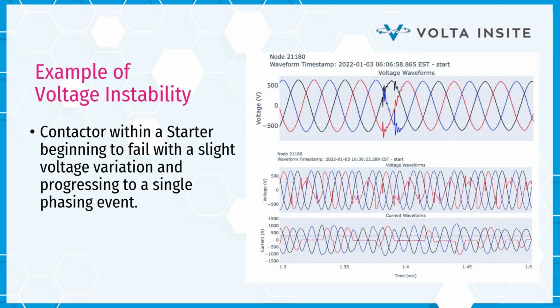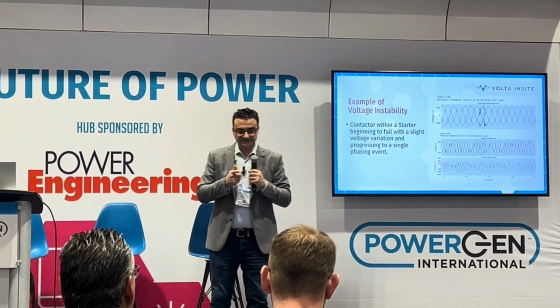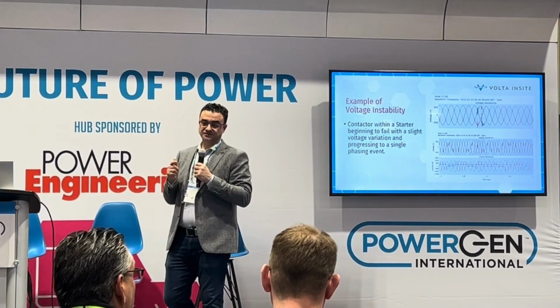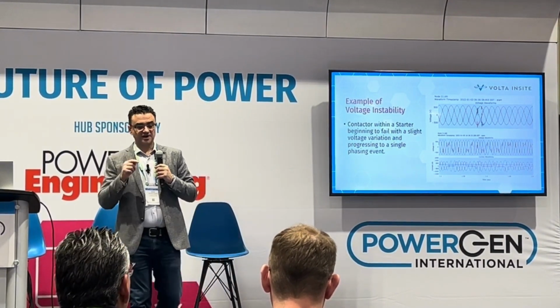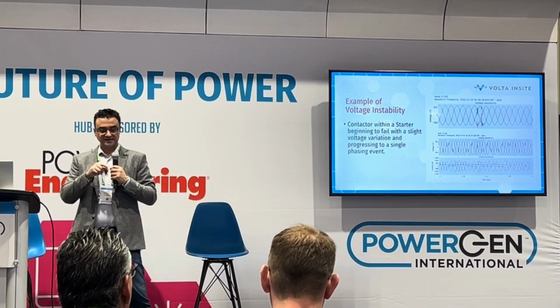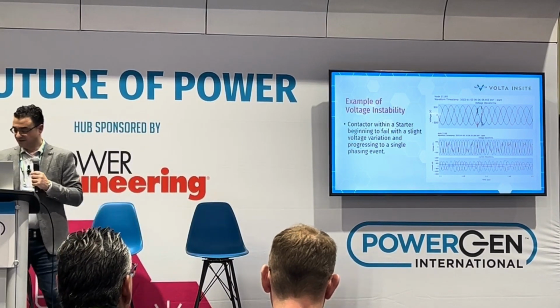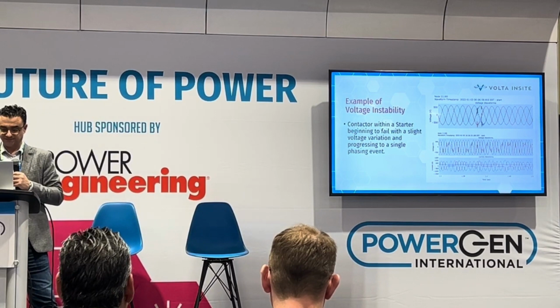So here's an example of voltage instability within a facility due to a contactor specifically. You'll notice on the top graph, those voltage transients happen at 6 a.m. in the morning, so we're able to capture that. And as the day progresses with a lot of stop-starts of this particular piece of equipment, by, I think, 10 hours later, we start single phasing. So we're starting to drop a complete voltage channel, and that is leading to single phasing of the motor. This motor did catastrophically fail eventually.